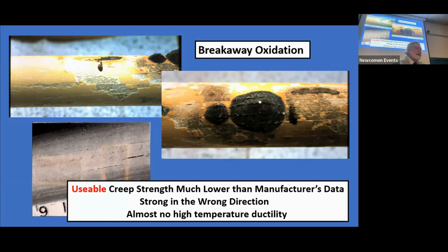We then brought it back to Britain, restarted the tests, and then we had a failure of the furnace about 600 hours later. And when we opened it up, we found these huge black incrustations where the alumina layer, which had been protecting the steel, had disintegrated. And what is happening there is just simply the steel itself is starting to corrode. And steel doesn't like air at 1100 C. But because of this, a lot of people started doing PhDs and the like to find out if they could improve this material. Well, they haven't. But it's made a lot of people very happy.